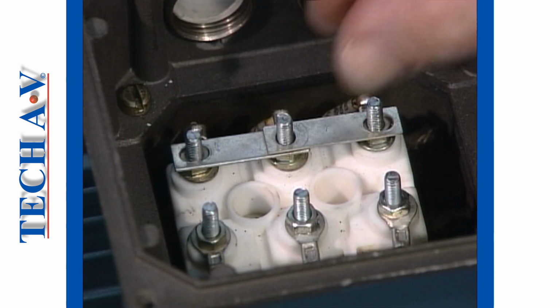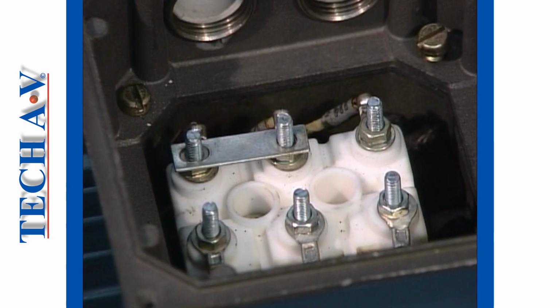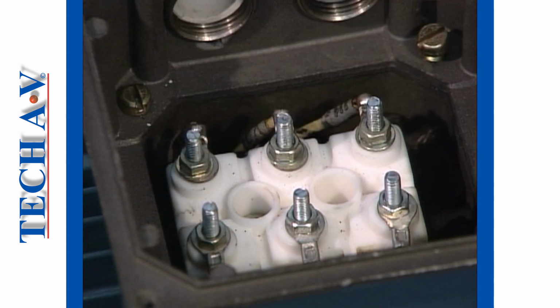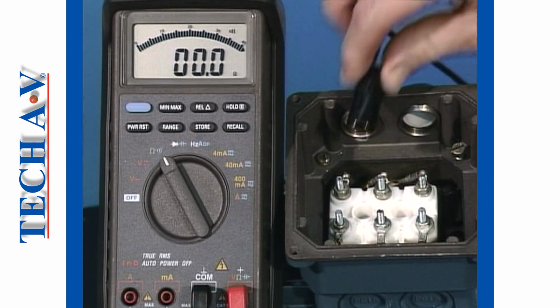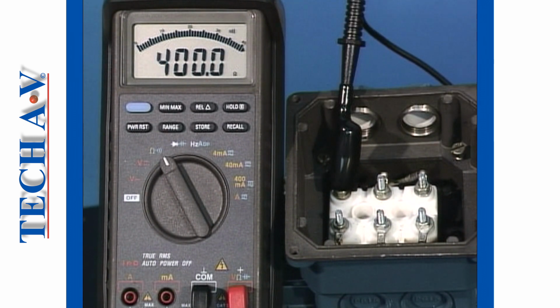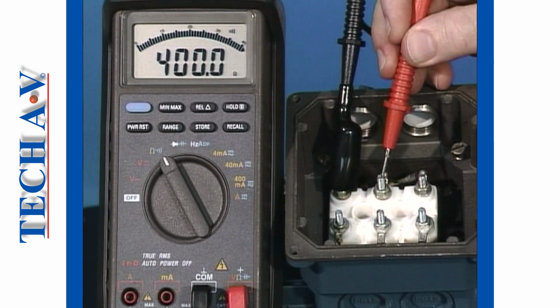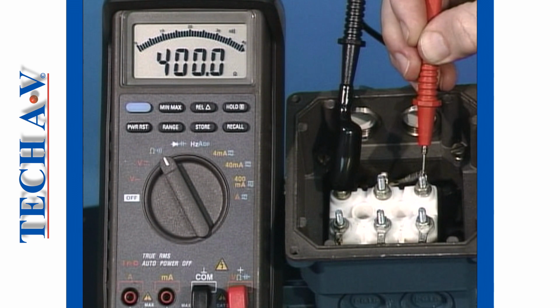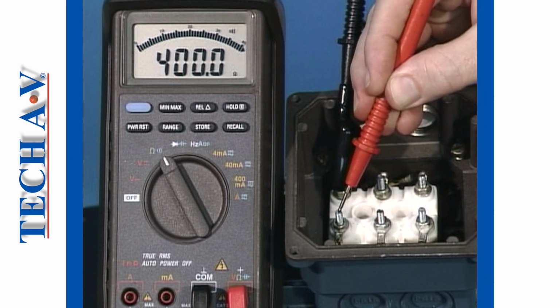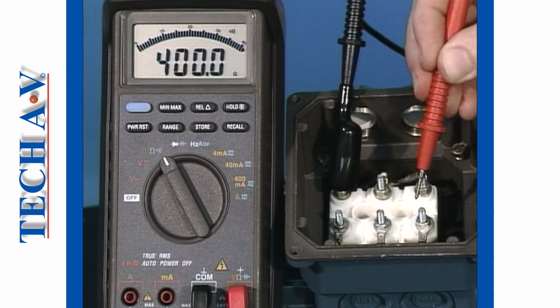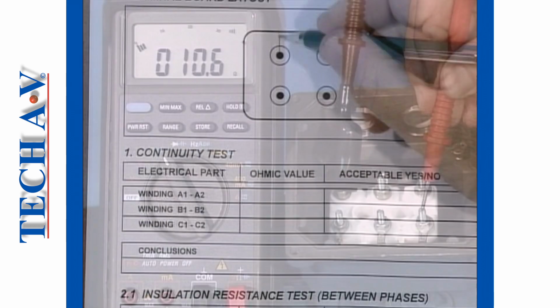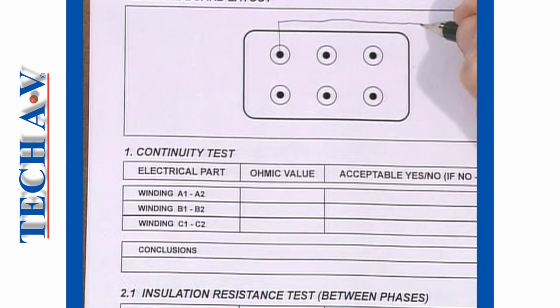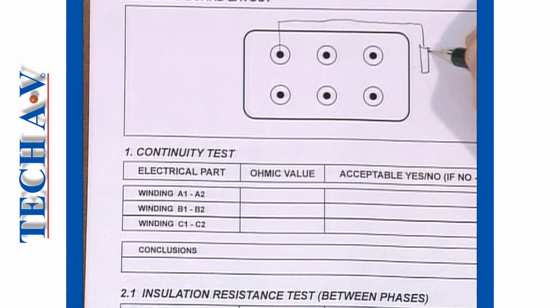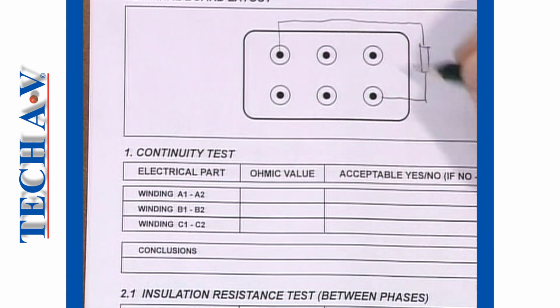Now remove any bridging pieces or links connected between terminal posts. Then clip one of the test leads to the top left-hand post. Probe all the remaining posts, moving from left to right across the terminal block until a reading is obtained. Using the checklist, record the position of the posts and the resistance readings.